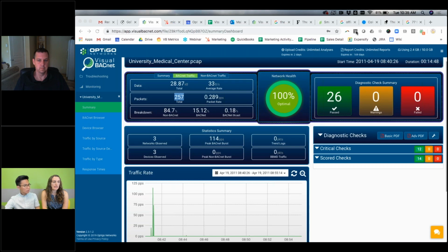Okay. Is it possible that there's another NIC that you could have captured on? Possibly, right. I have to go back now, do a Wireshark capture again to see where I get obviously a lot more than 3 devices on there. Yeah. How about the BACnet port? Are you using the standard BACnet port? Yes, right.